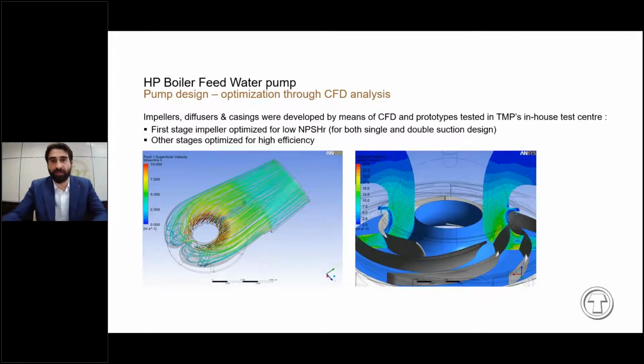The geometry of the impeller, diffusers, and casings used in this pump has been used also several times in other projects and plants, and has been developed in-house using CFD and then tested with prototypes in our test center. The first stage impeller has been optimized, as I've already said, for low NPSH required, but we have the possibility to install a double suction impeller with even higher suction capabilities. And the other stages are optimized for a very high efficiency.